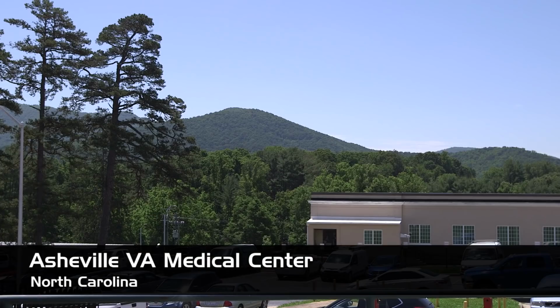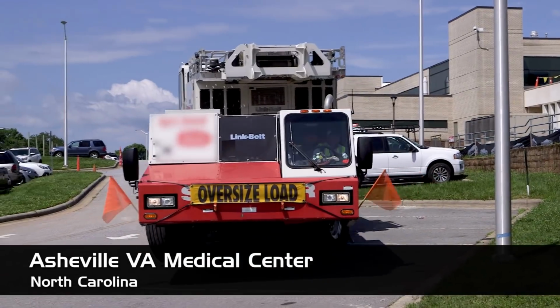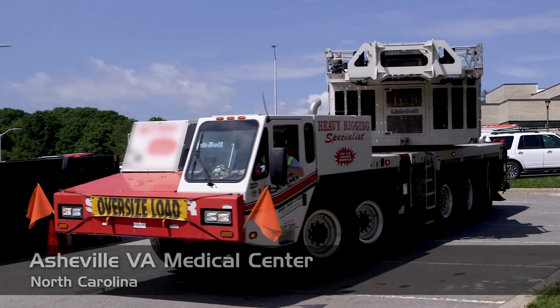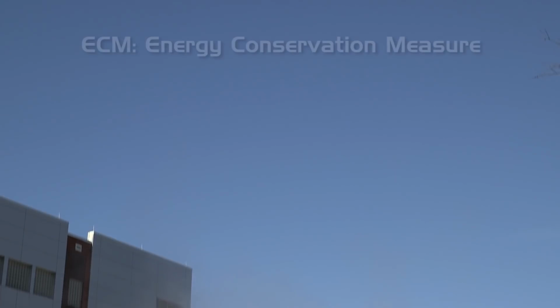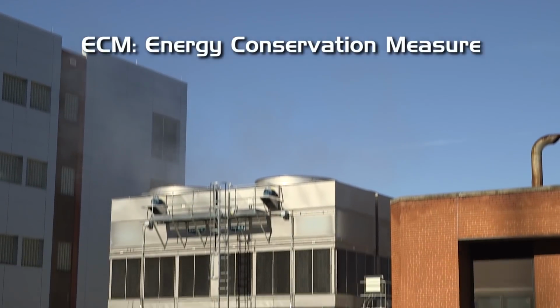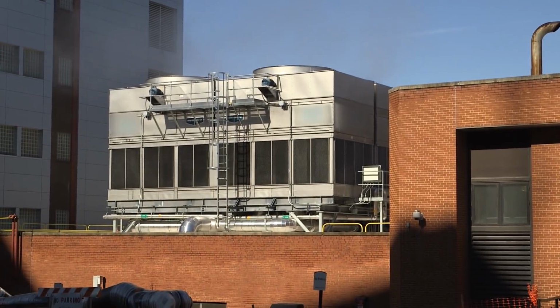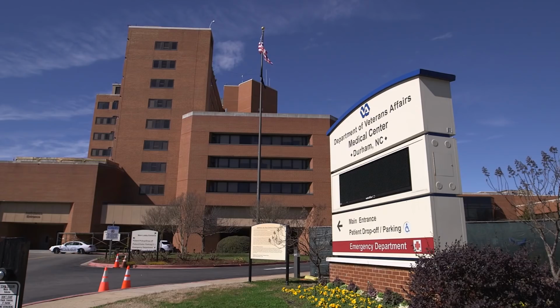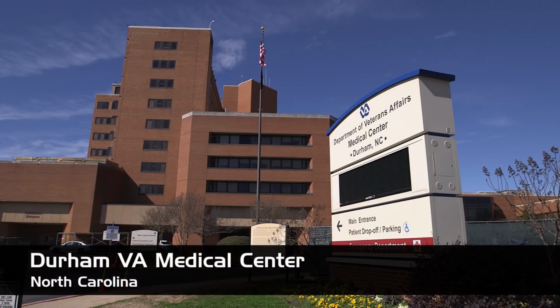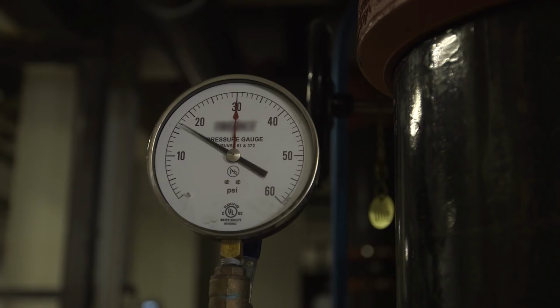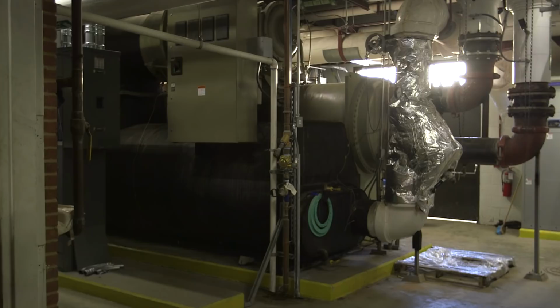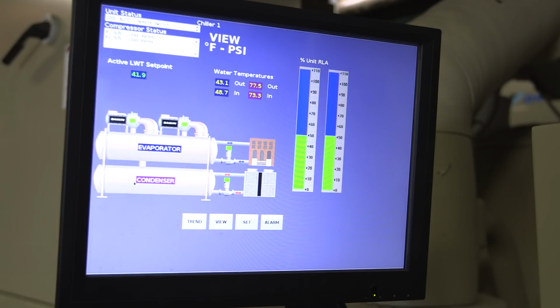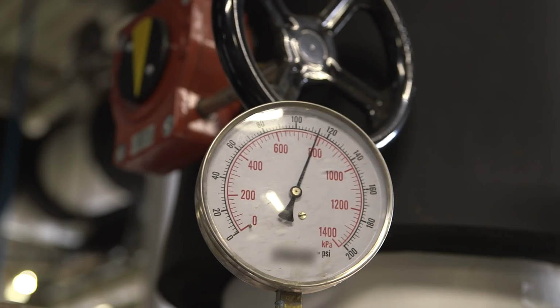Another great advantage of an ESPC is you're able to modify the contract as needed. For instance, at Durham, the original ECM for the chiller plant included one of the two cooling towers. During construction, the other cooling tower had a major failure, and it was more economical to replace it than repair it. That plant also once operated at a much lower temperature, which consumes more energy. We're able to raise the temperature now because we're able to move the water to where it needs to be.